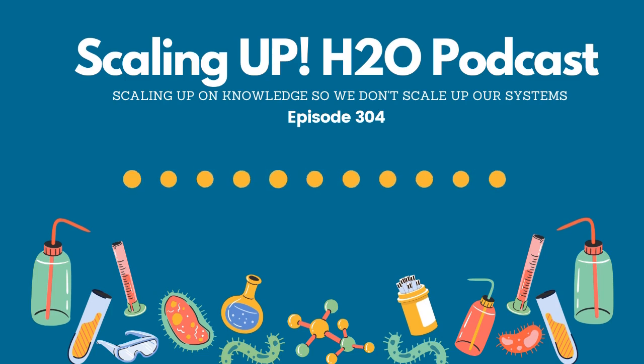Other water treaters have sent corrosion coupons to me without the starting weight, and then they get upset that I can't weigh them. Well, I can give you a final weight, but if I don't know what the starting weight is, I can't tell you how much metal loss between A and B there was, and I can't do my math then, and I can't get you a number. So you have to make sure when you have these envelopes that you take care of them, you store them properly, and what I mean by that is you do not lose them.